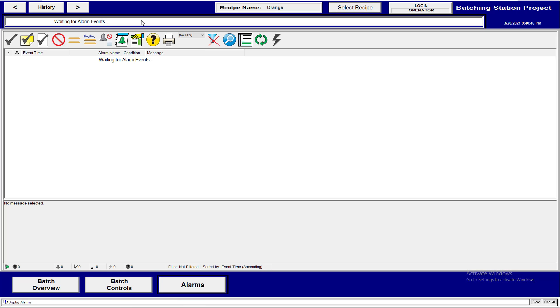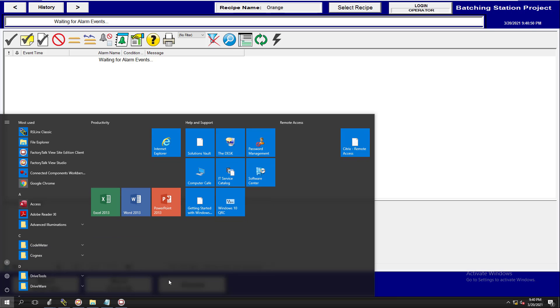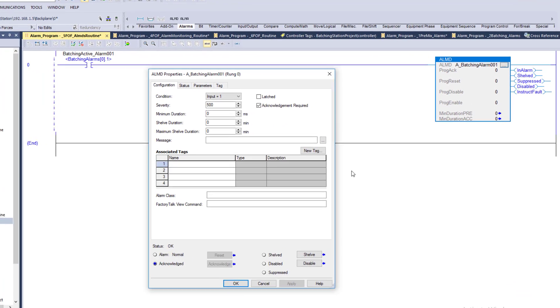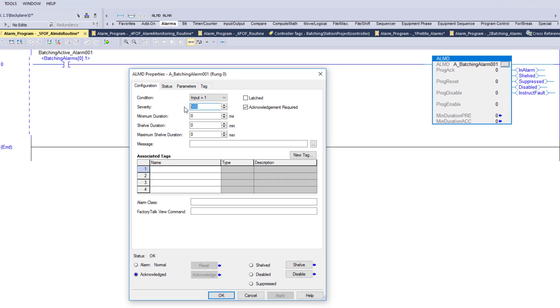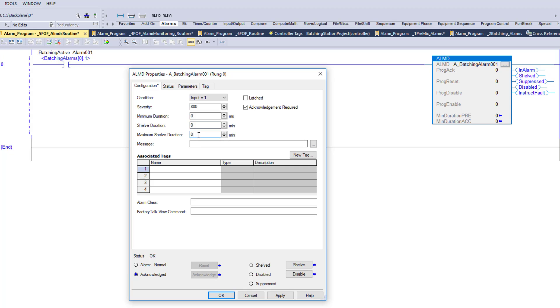This is how we communicate from our PLC to our HMI — using this screen and the top header bar. To save time and effort: the severity basically has a color scheme on the back of that HMI screen. I like to have severity anywhere between 800, if it's important, or 1000 — 1000 would be red. The minimum duration is how long it has to be active before this fires; I like to trigger that at zero. The shelf duration I don't mess with.